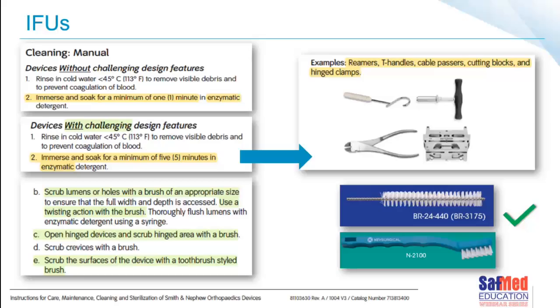So back to that orthopedic company's view. Remember what the manufacturer has to do before they can actually sell you the device: they take all of the instruments, all of the things that they've now manufactured, and they contaminate them with a known amount of microorganisms and soils. They then put the devices through a series of cleaning processes.